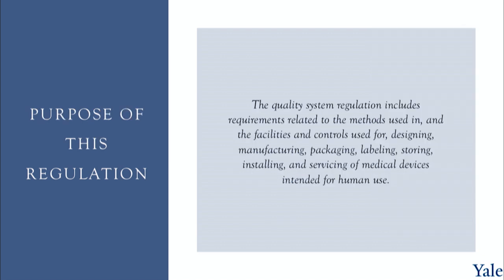The purpose of this regulation, and we're going to quote directly from the document: the quality system regulation includes requirements related to the methods used in the facilities and controls used for designing, manufacturing, packaging, labeling, storing, installing, and servicing of medical devices intended for human use. The word I want to highlight here is the word design. The regulation doesn't begin, as in the myth that we talked about last week, once the thing is being tested. The process begins at the design. And this is an important component of this story.